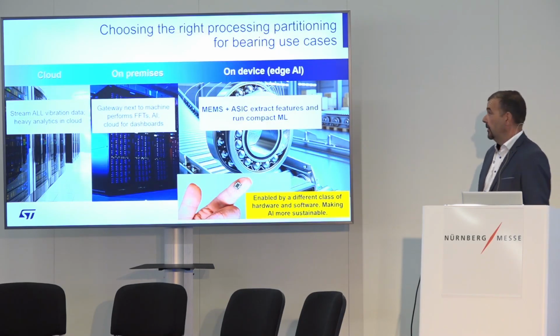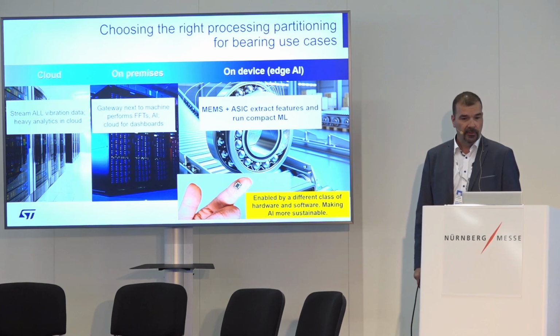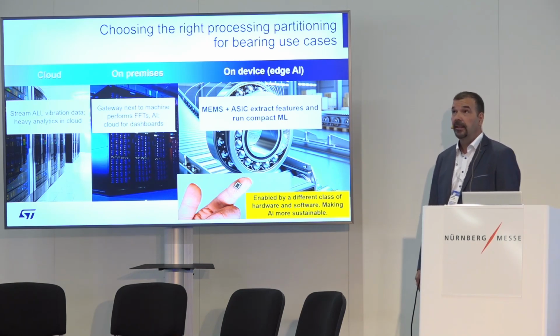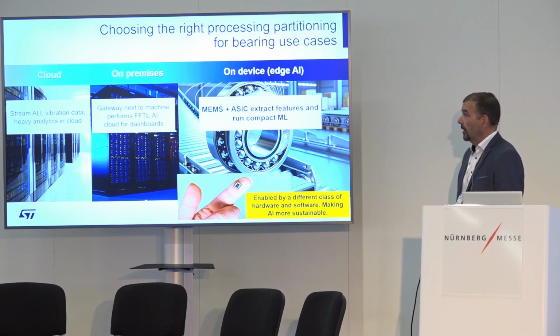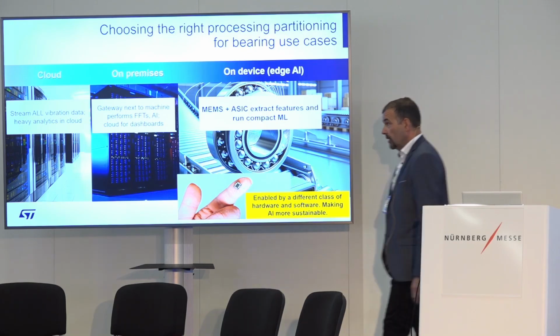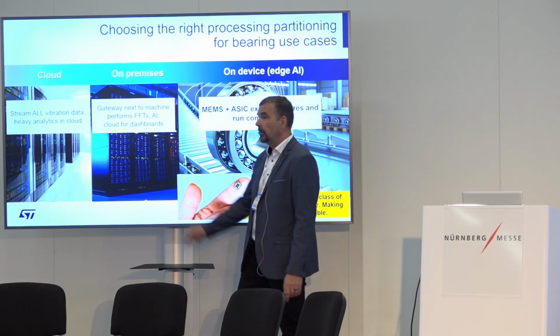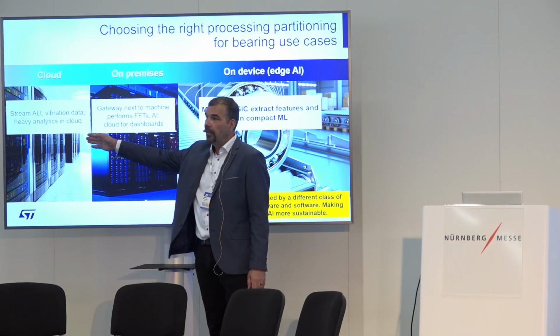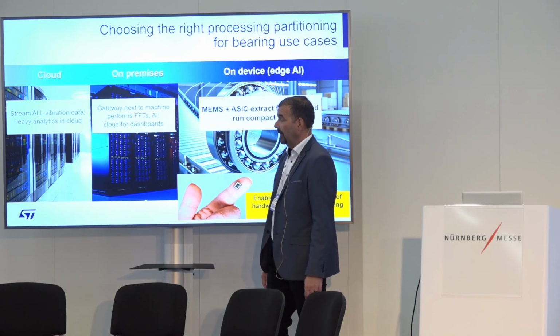The last part was also touched on by my colleague. It's about the amount of data and calculations of similar things like FFT or AI inside the cloud. In case we went to the cloud, we would need to stream all data from the vibration sensor, which is a huge amount of data, and it does not make sense.